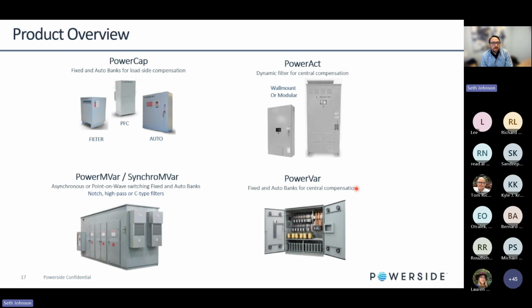So we have our Power Cap product series, which we can do in standard power factor correction cap bank, like a static capacitor. We have our filter. We have our Power Cap Auto, which is a low-cost version of an automatic switching capacitor bank. And then, of course, our active filter products over here on the right, which we introduced into the market in 2015, which continues to have a very big growth potential, and the trajectory for this product is going to continue to be quite massive in North America as utilities continue to look for and search for customers who may or may not be meeting the point of coupling compliance standards such as IEEE 519.